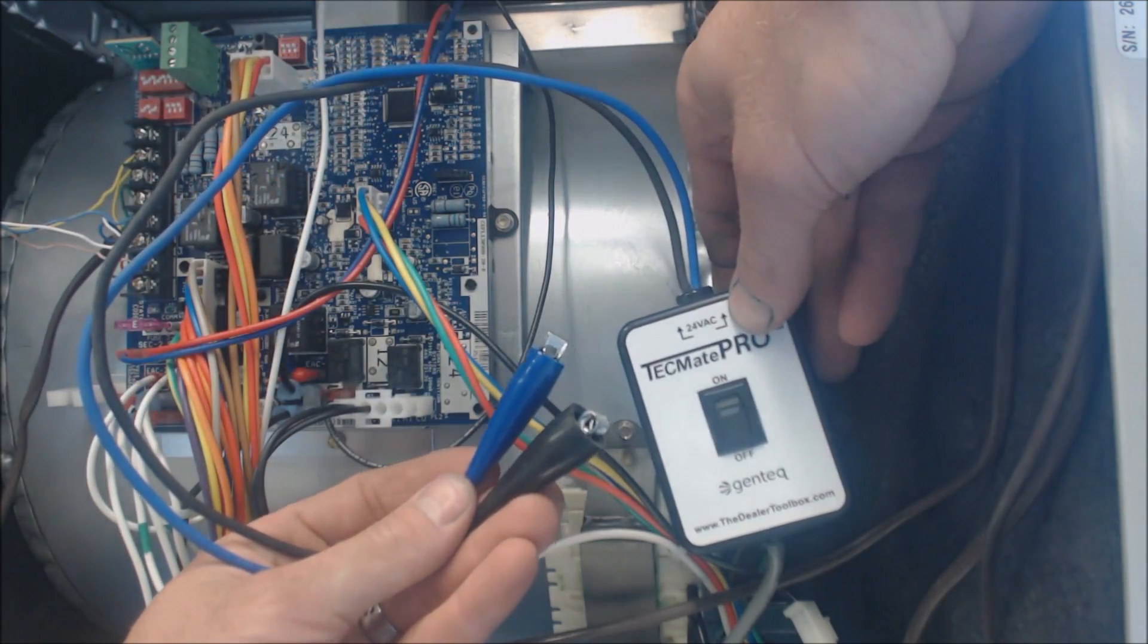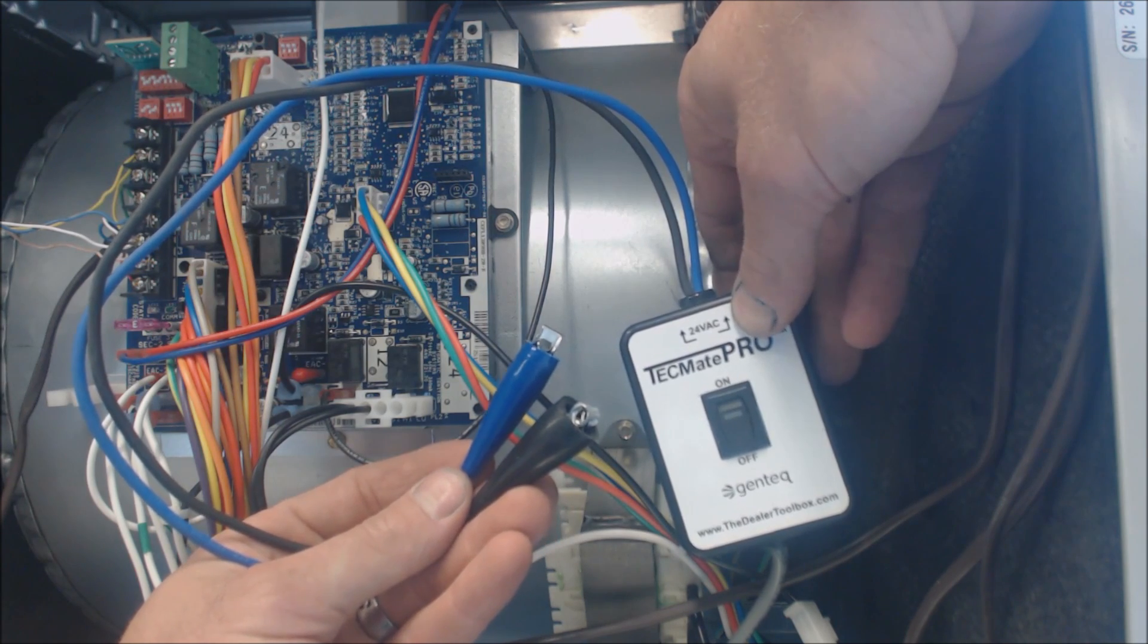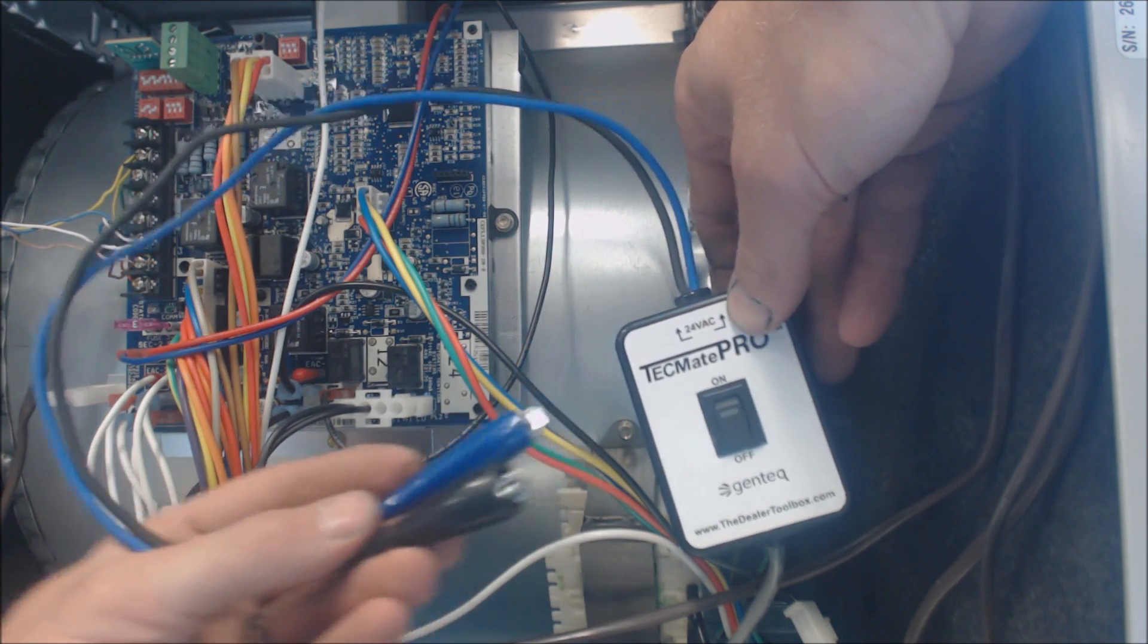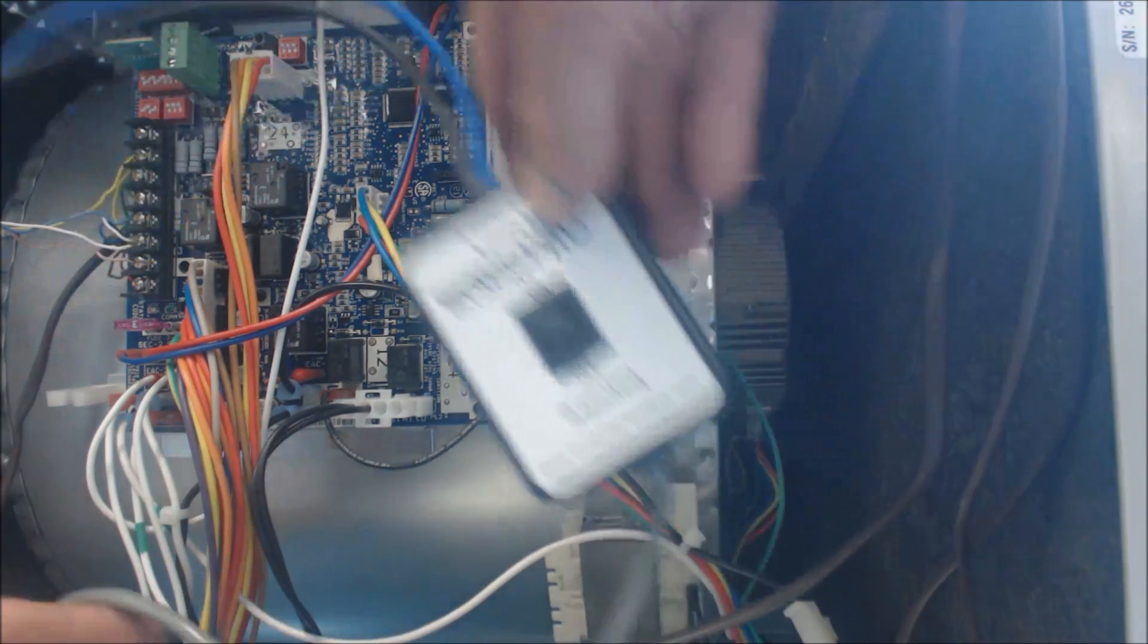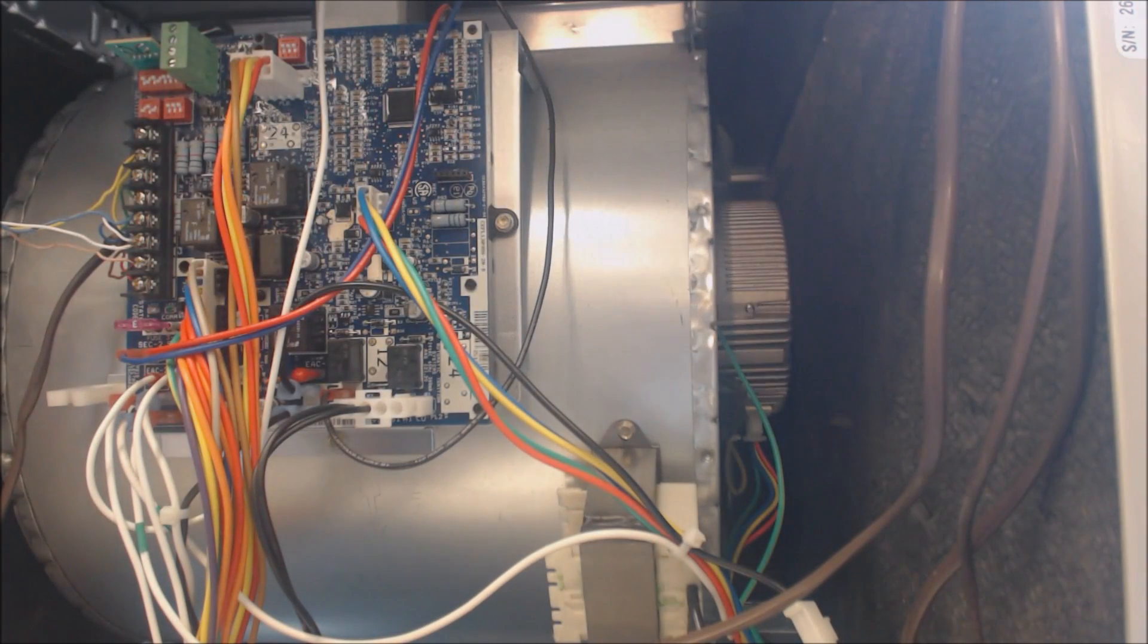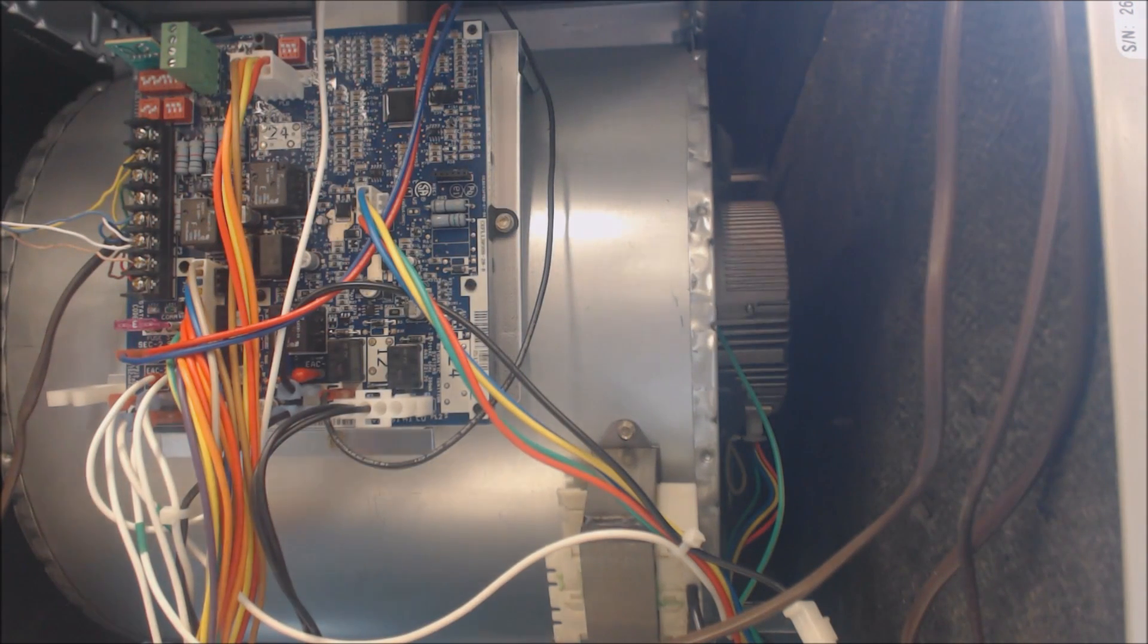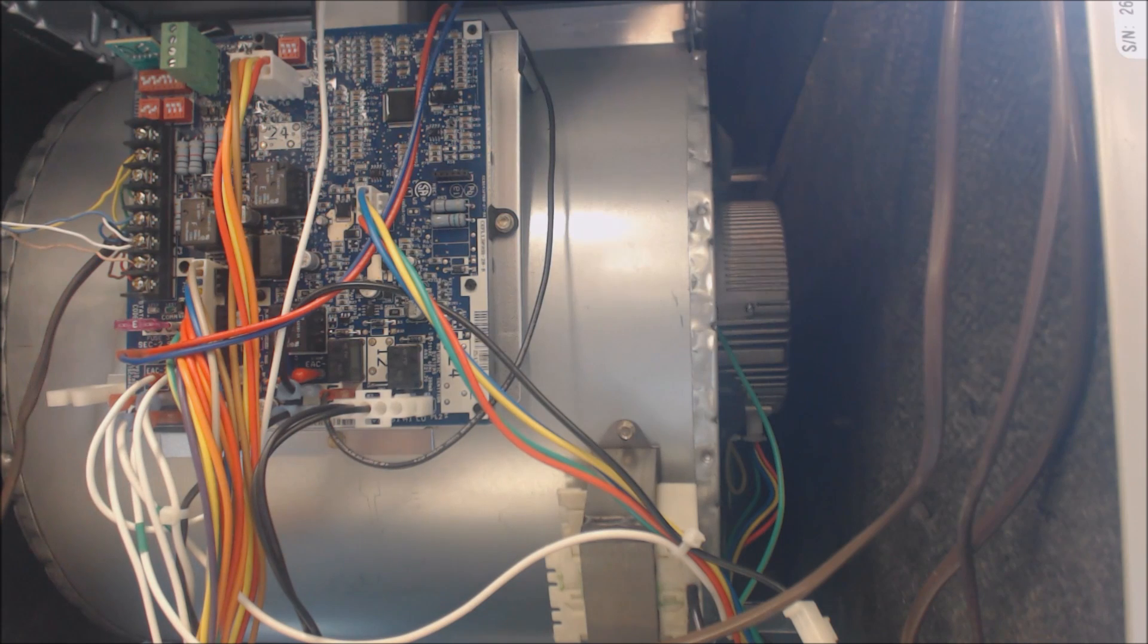Then you have these two alligator clips, and they clip onto the red and common on the control board. Just so you know, anytime you have the power on, on a furnace, you're always going to have 120 volts going to the variable speed blower motor housing.